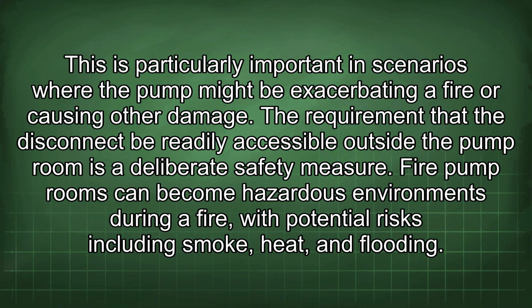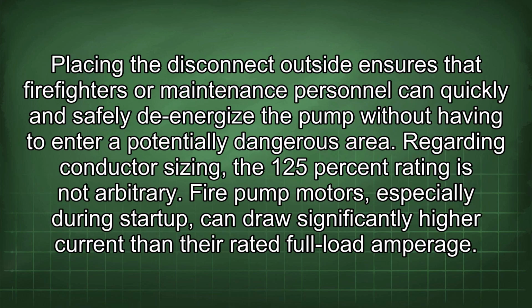The requirement that the disconnect be readily accessible outside the pump room is a deliberate safety measure. Fire pump rooms can become hazardous environments during a fire, with potential risks including smoke, heat, and flooding. Placing the disconnect outside ensures that firefighters or maintenance personnel can quickly and safely de-energize the pump without having to enter a potentially dangerous area.